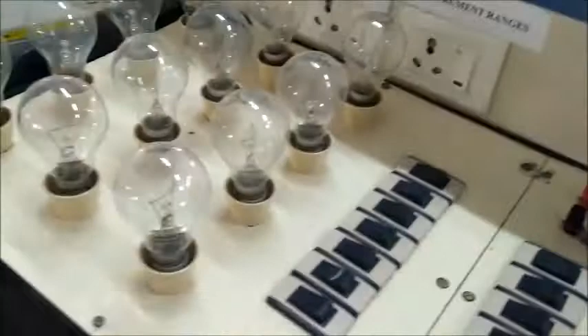And you will see the lamp load. This is your lamp load. Each bulb is 100 watts. Clear? We are going to have 12 lamps. Now check whether your auto transformer is in the minimum voltage position. Now turn on. Now gradually increase the voltage. You can apply the maximum voltage, not an issue.